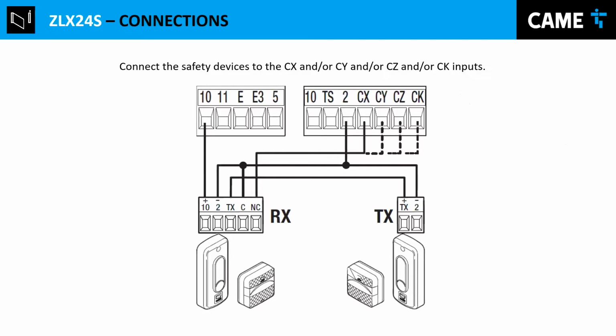This is the way to connect photo cells. Photo cells basically need power and they give a normally closed contact. The power in this case is given by pin 10 and 2, but some photo cells you can connect also to 10 and 11, but it depends on the photo cell, so you have to follow the diagram for your photo cell. In this case, we have power between 10 and 2, and also the contact, normally closed, we can connect between 2 and CX or any other pins.